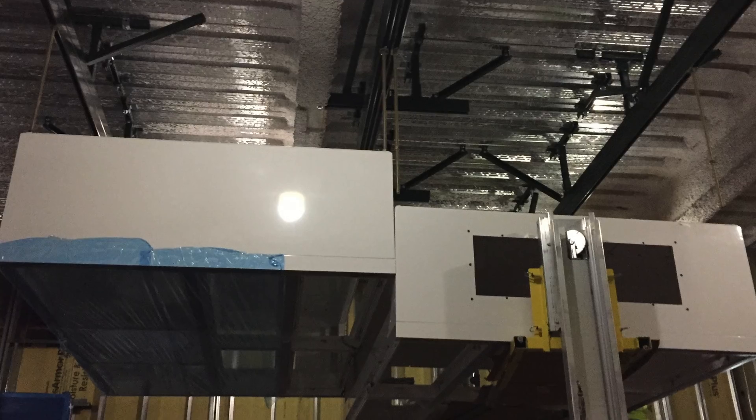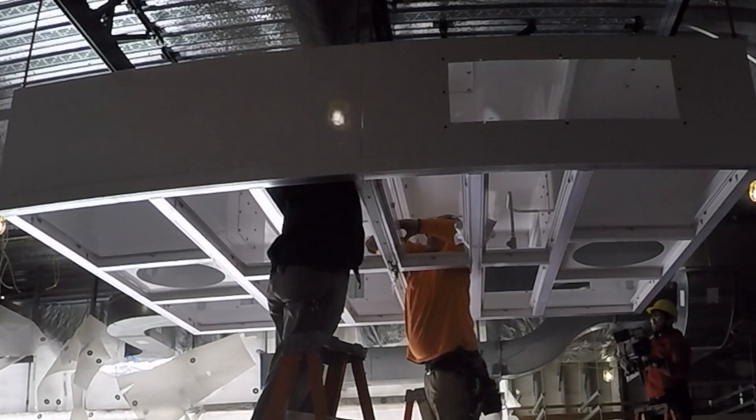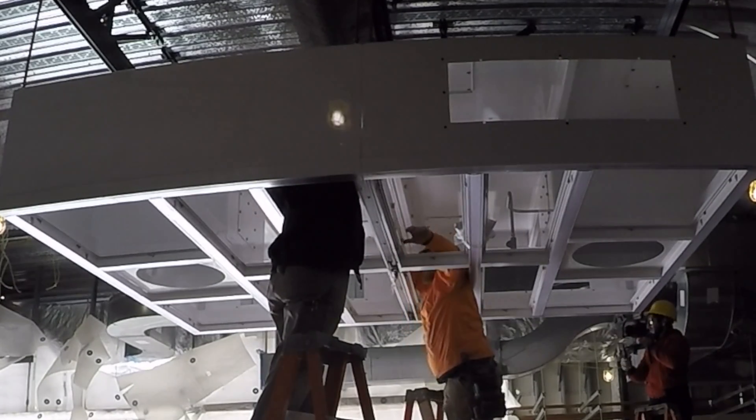This particular project design is serving the operating rooms and is comprised of two factory built modules which are erected and then bolted together to create one single large diffuser to deliver roughly 2100 CFM of laminar airflow over the sterile field.